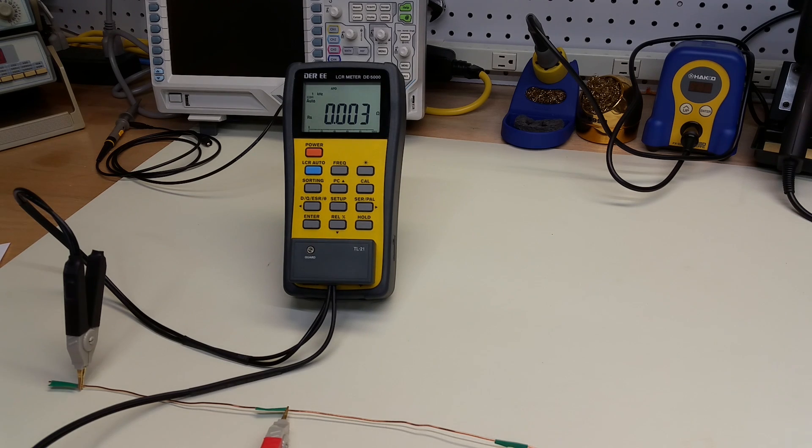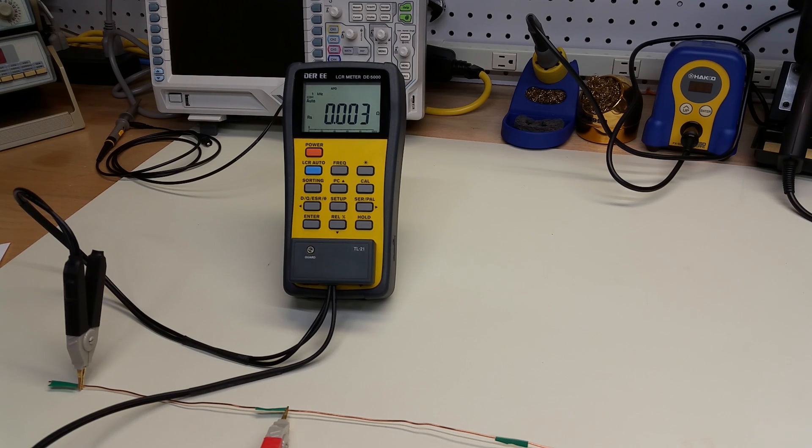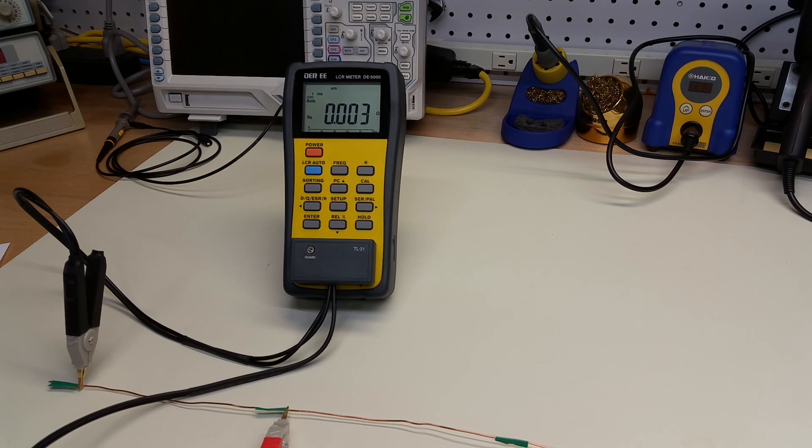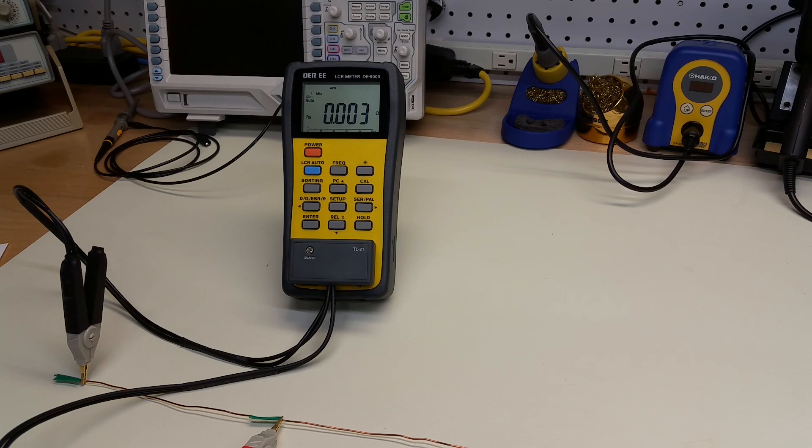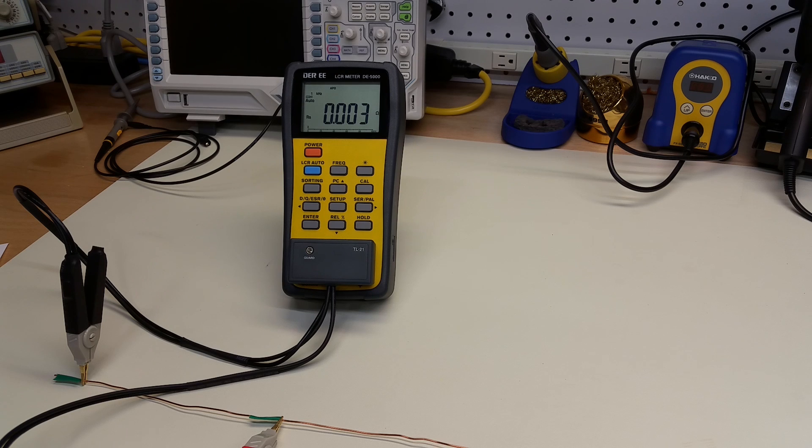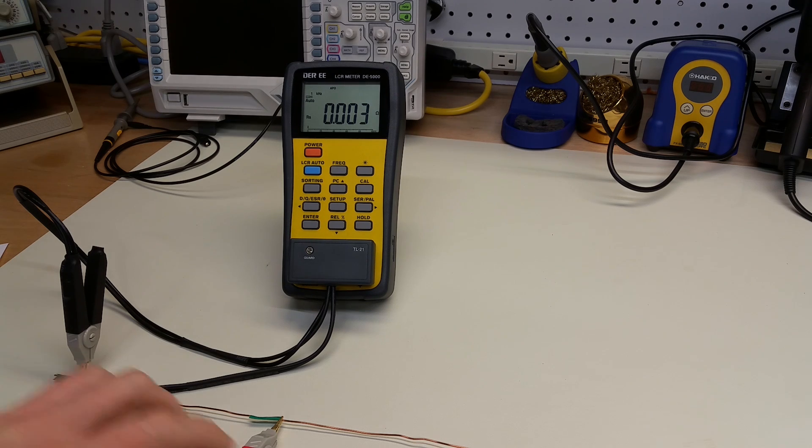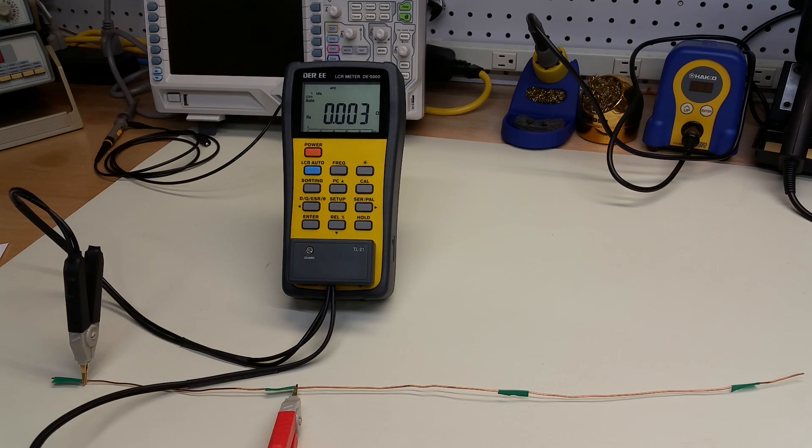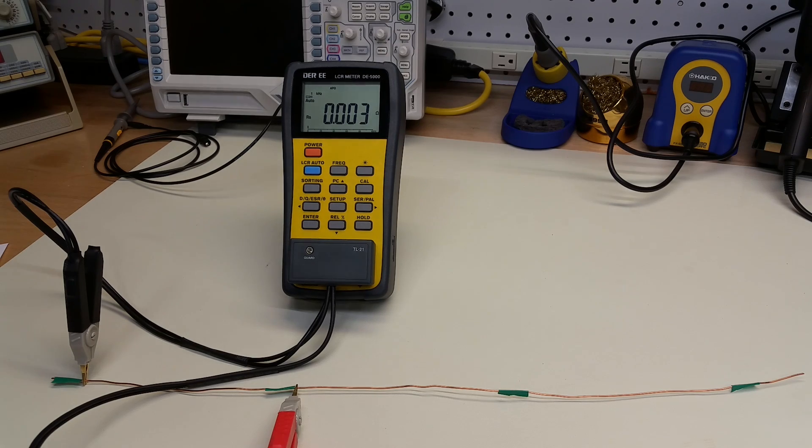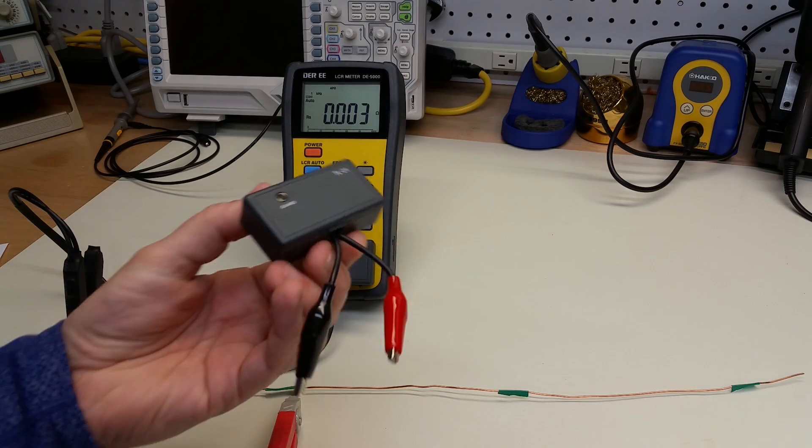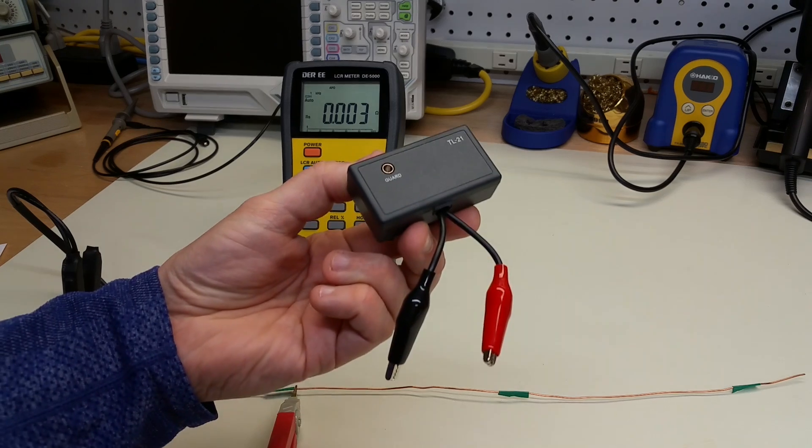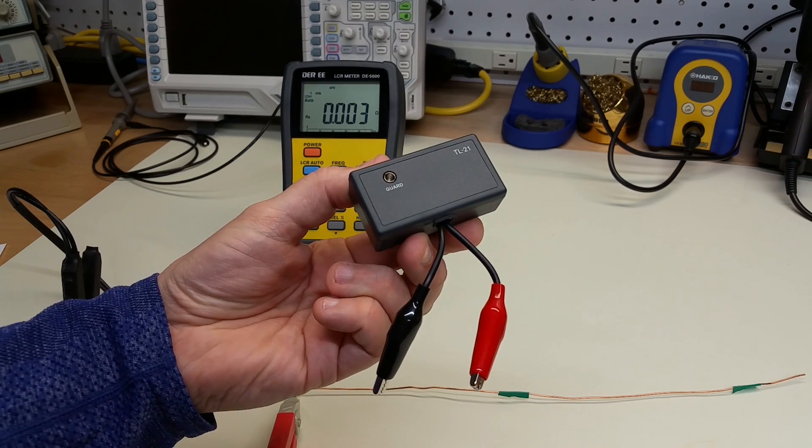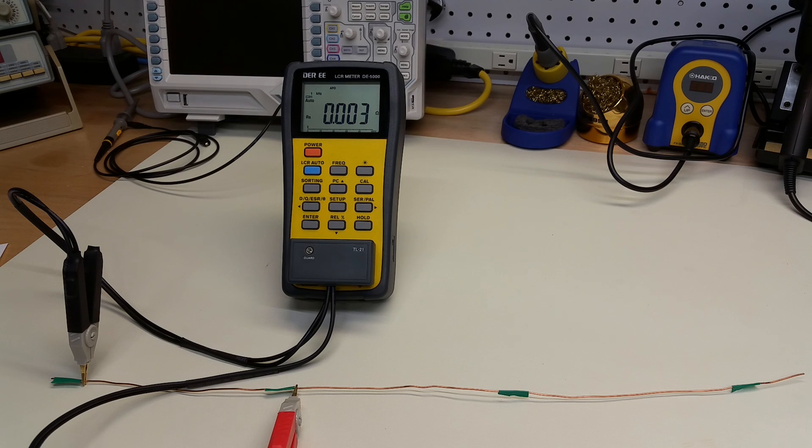So, this is behaving exactly the way that we would expect it to do after installing the Kelvin clamps and running through the calibration procedure. So, what we did in the experiments that I'm about to describe is we measured using the DE5000 elements or lengths of this wire using the Kelvin clamps. But then we also used the original two-wire alligator clip assembly.